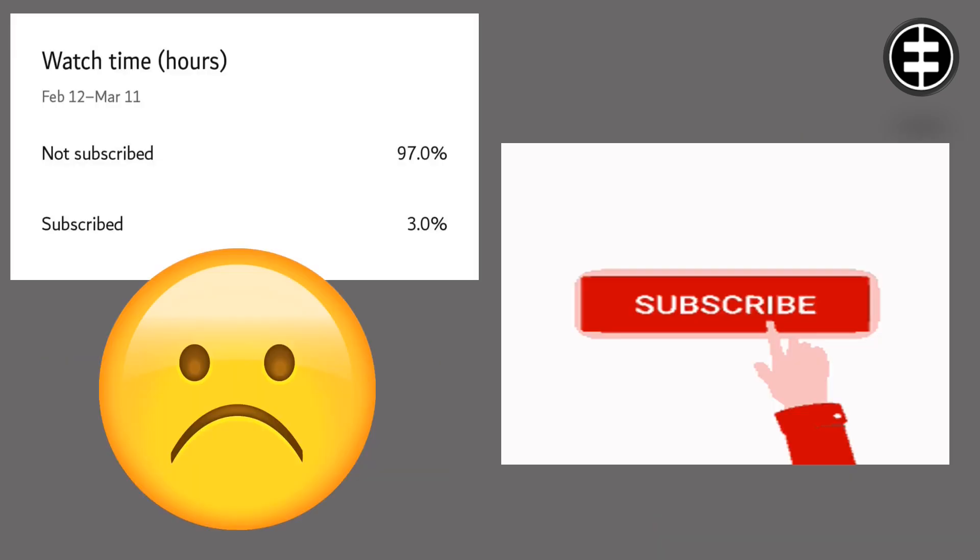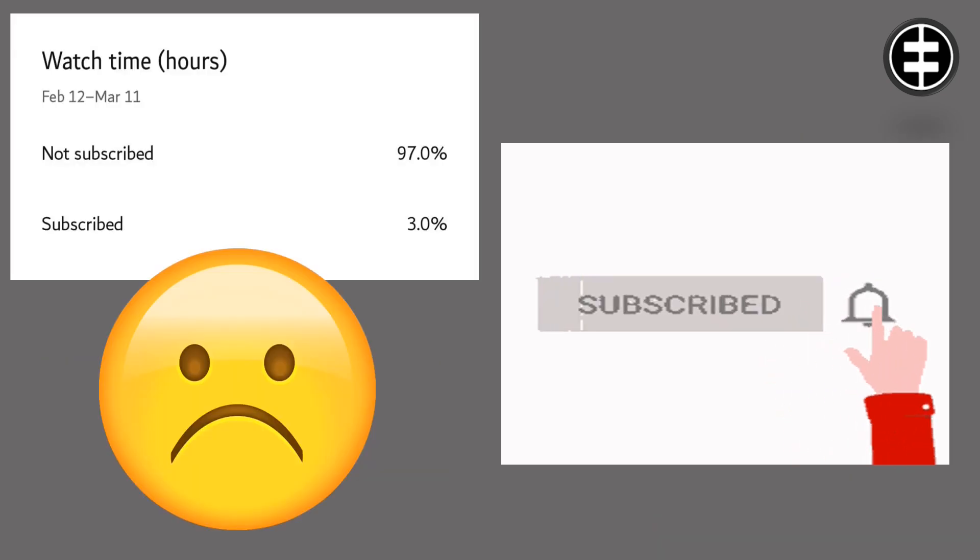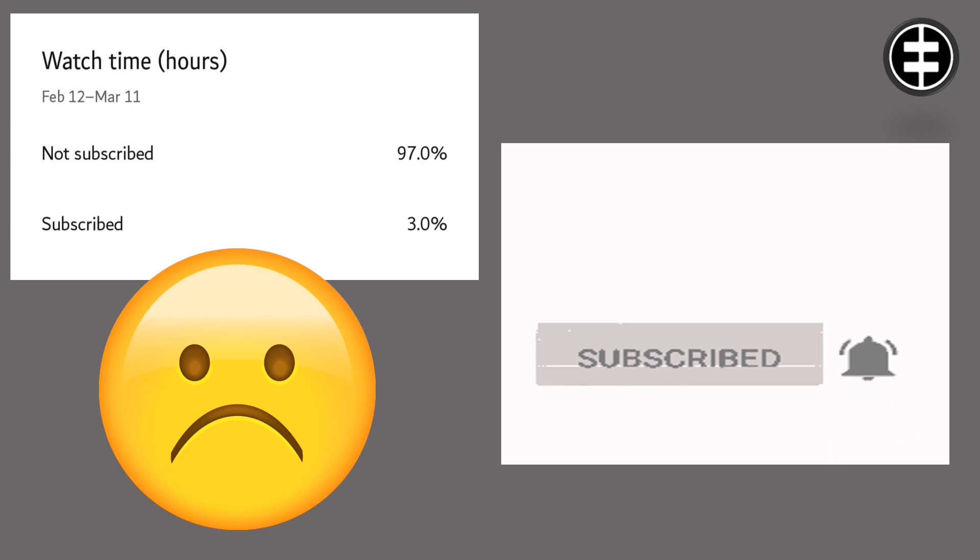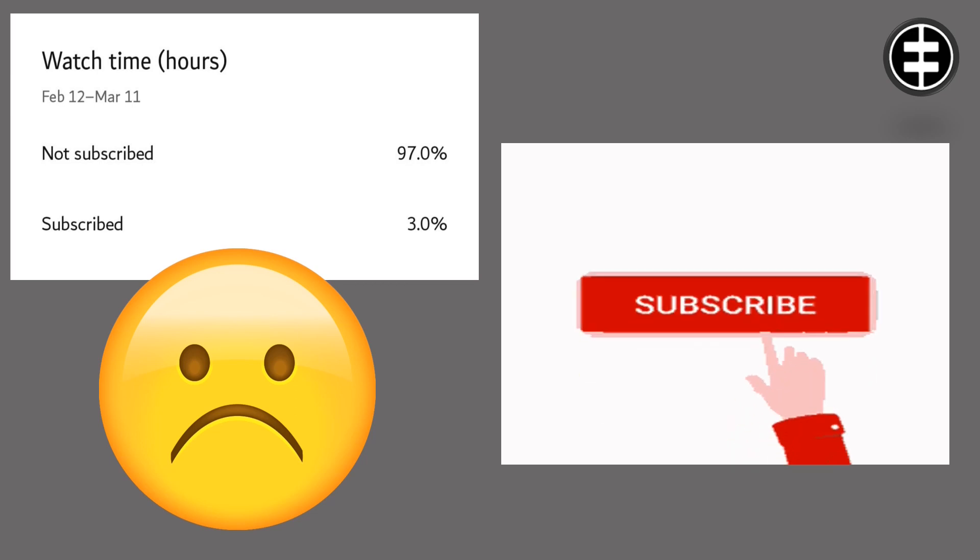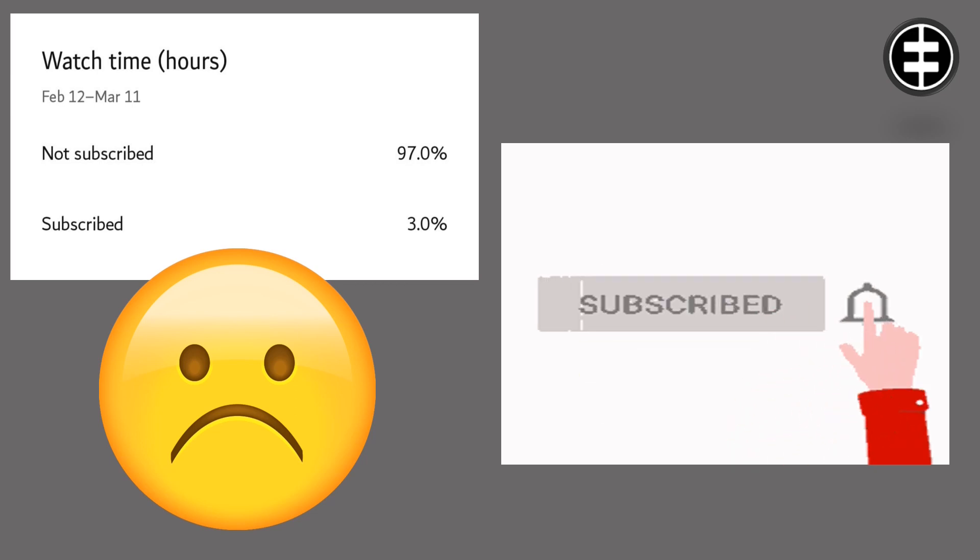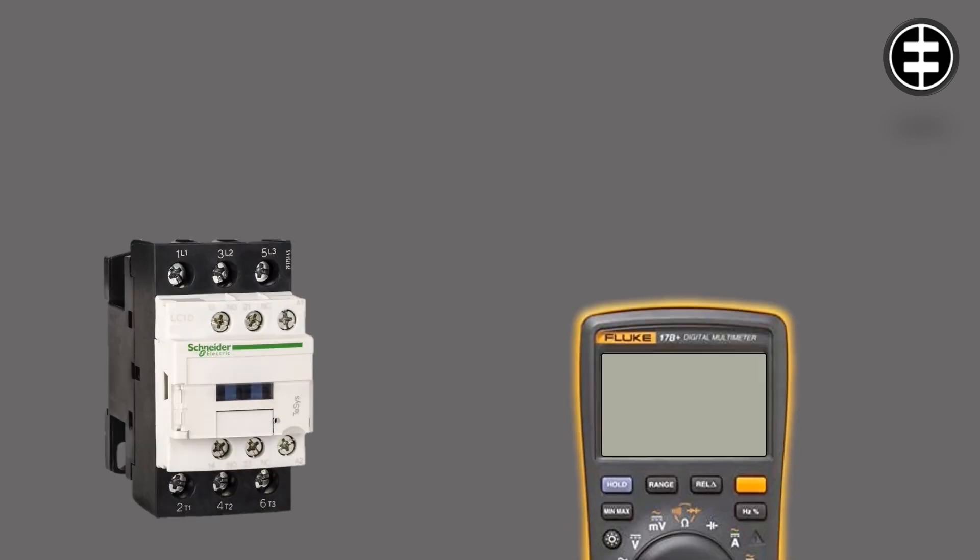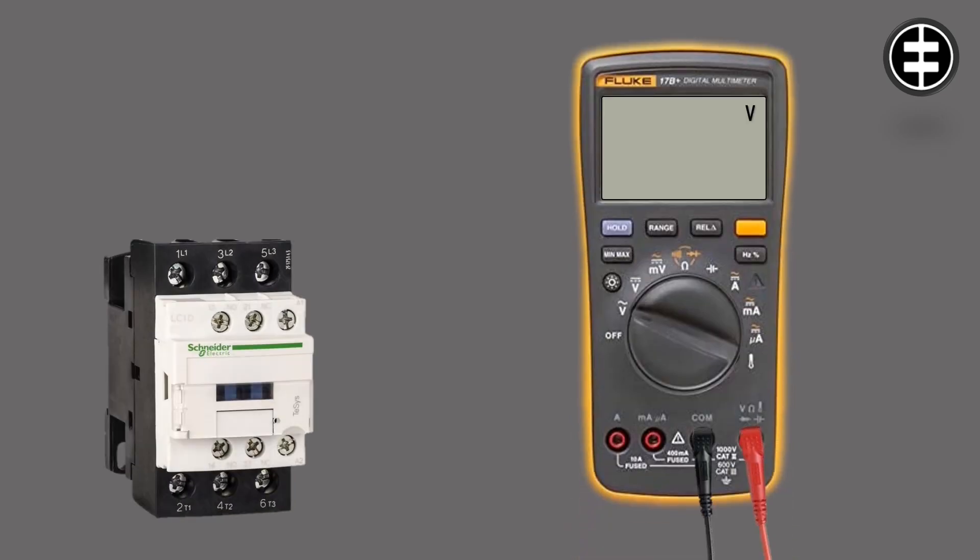Before continuing, 97% of people watching our videos forget to subscribe, so subscribe now. Measure the coil voltage just as the contactor is powered up. Put the multimeter probes into the contactor terminals A1 and A2, power up the contactor, and check the voltage measurement.